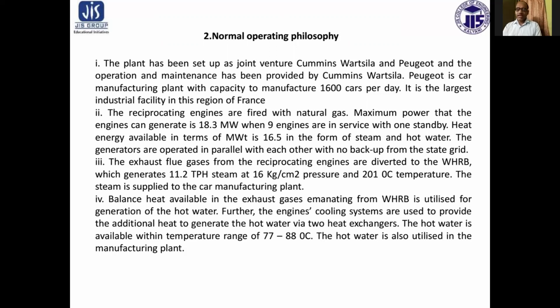The maximum power that the engines can generate is 18.3 megawatt when 9 engines are in service with 1 standby. Heat energy available is 16.5 megawatt in the form of steam and hot water. The generators are operated in parallel with each other with no backup from the state grid.